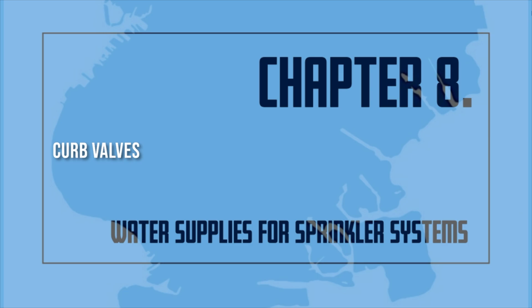The main water supply for sprinklers may also be controlled by an OS&Y, outside stem and yoke valve. The valves are found just inside the building wall on the main riser, or outside in protected pits. It is easy to tell at a glance if the valve is open or shut. When the stem is all the way out, the valve is open. When the stem is all the way in, the valve is closed.